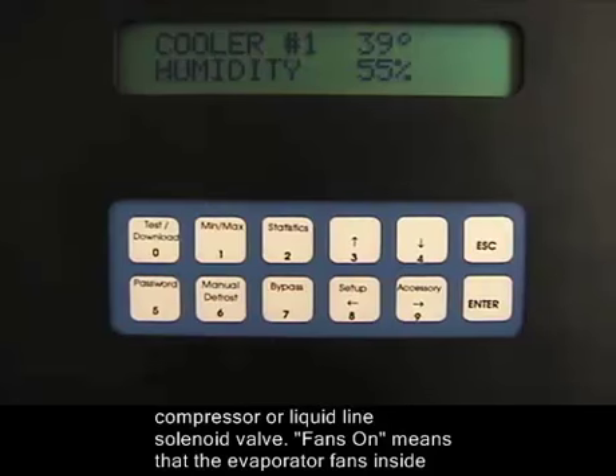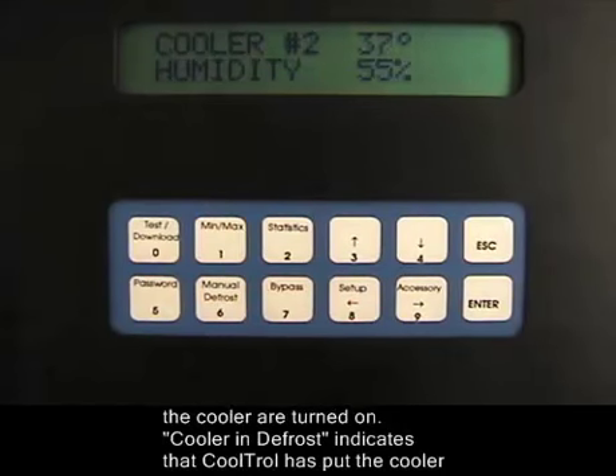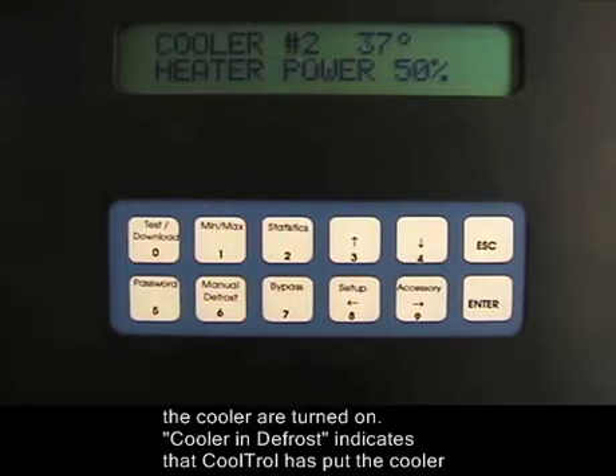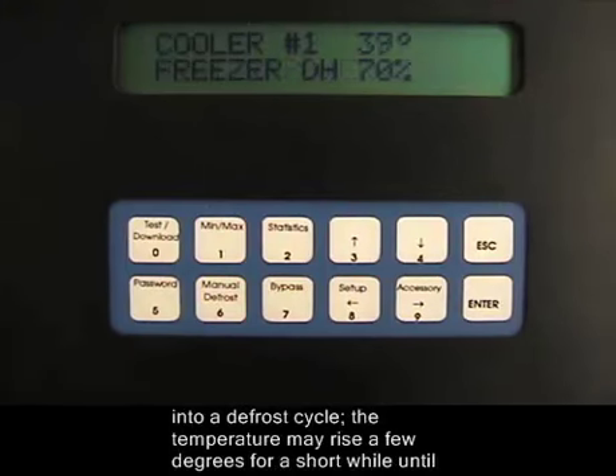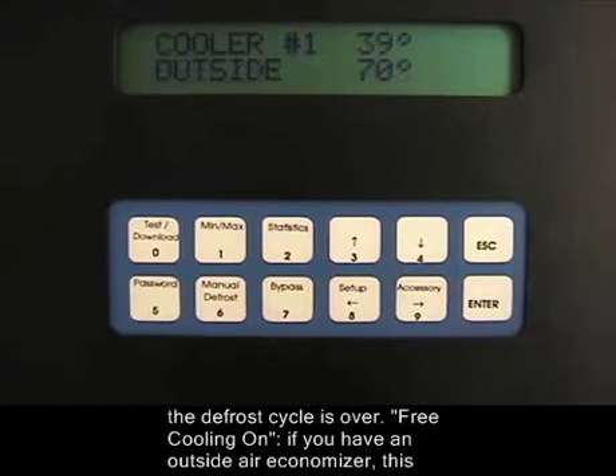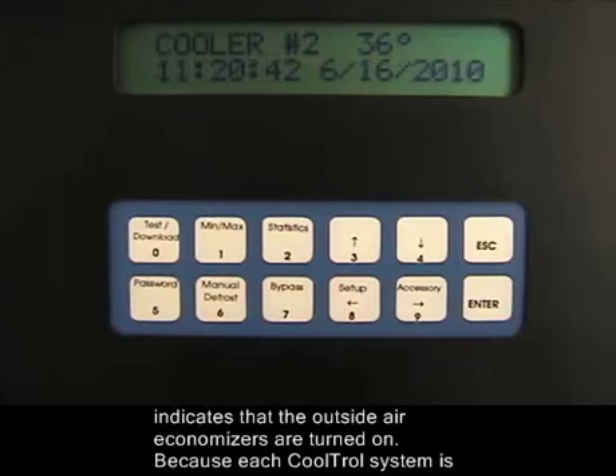Fans on means that the evaporator fans inside the cooler are turned on. Cooler in defrost indicates that CoolTrol has put the cooler into a defrost cycle. The temperature may rise a few degrees for a short while until the defrost cycle is over. Free cooling on. If you have an outside air economizer, this indicates that the outside air economizers are turned on.